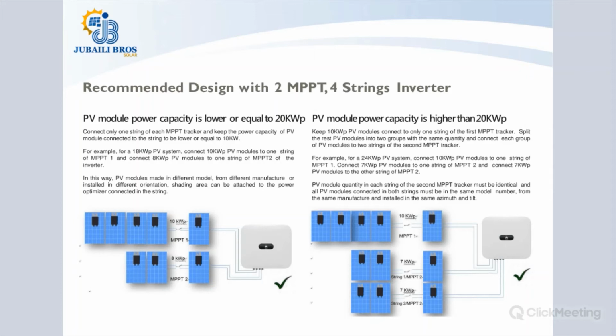Now, in the scenario on the right, we are assuming that you are connecting a DC wattage that is slightly higher than the inverter rating. Here we are doing 24 kilowatts, whereas before it was 18 kilowatts. For the 24 kilowatt system, you connect the maximum to the first MPPT, that's 10 kilowatts. For the second MPPT, the balance would be too high, because if you do 10 kilowatts here, you get 14 kilowatts, which is more than the maximum allowable per MPPT. So you can split it into 7 for the two strings that are supposed to join the second MPPT, and it's also very much recommended. So if it's a lower wattage than the inverter rating, you could do it this way. If it's a higher wattage than the inverter rating, you could also do it in this manner, and it's very much acceptable.